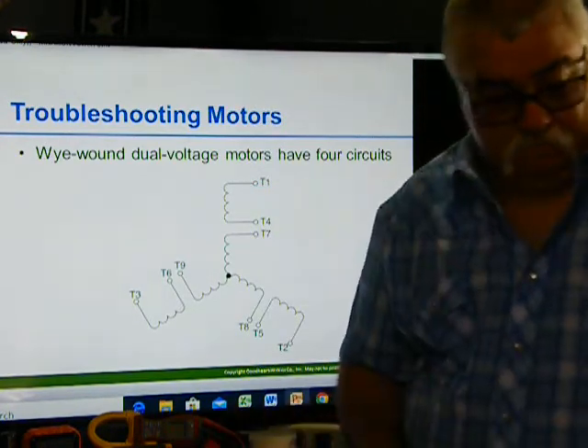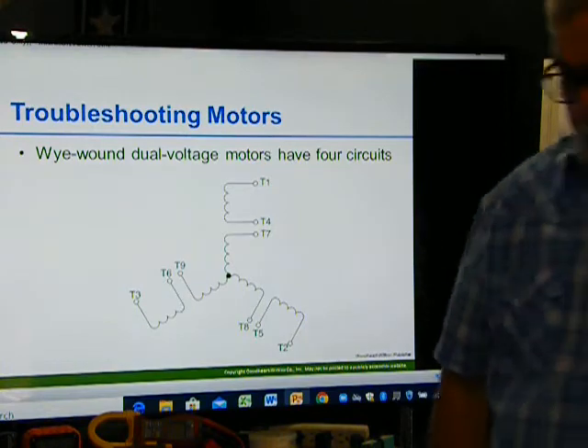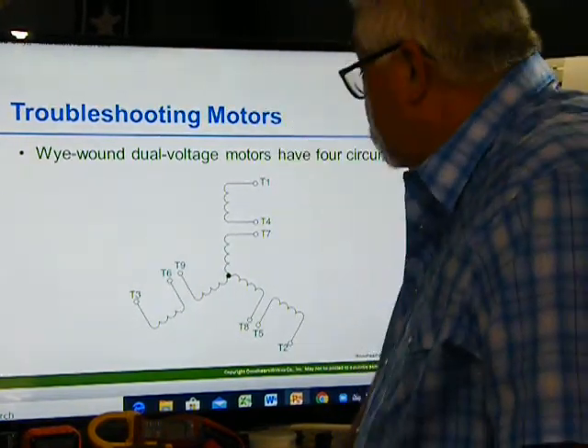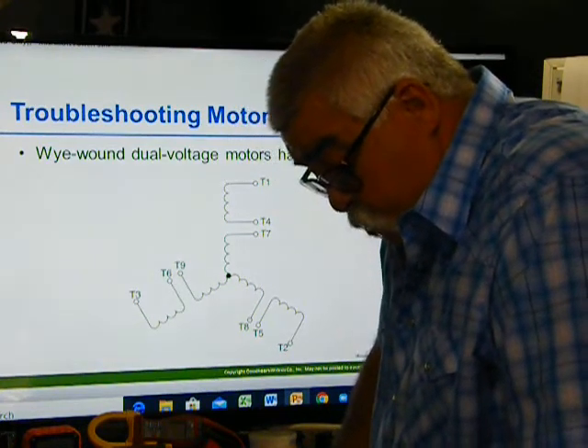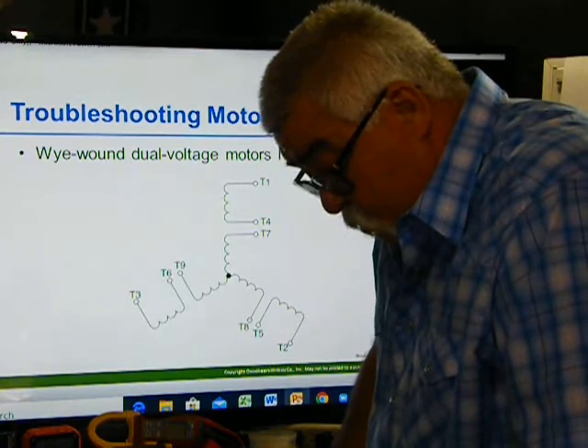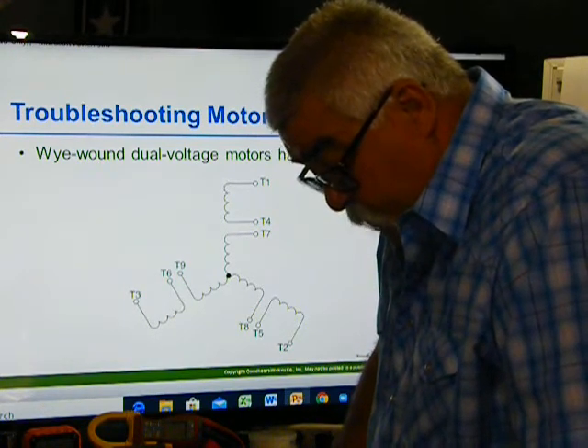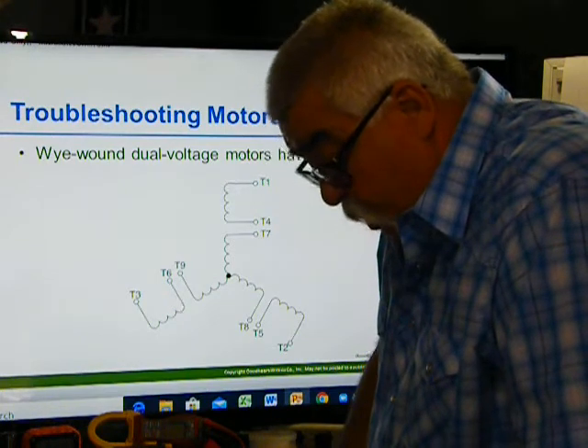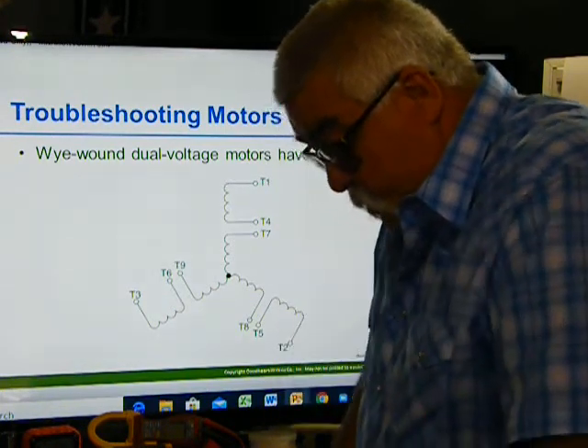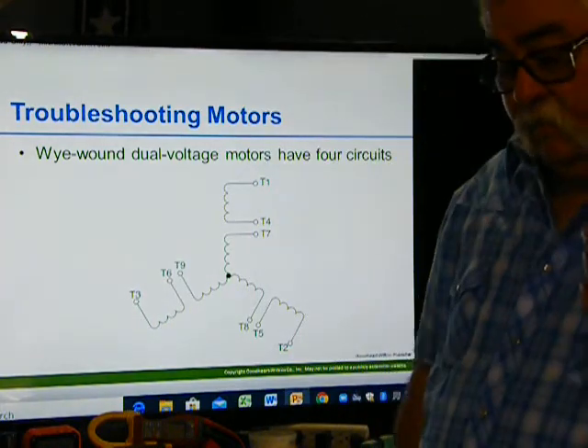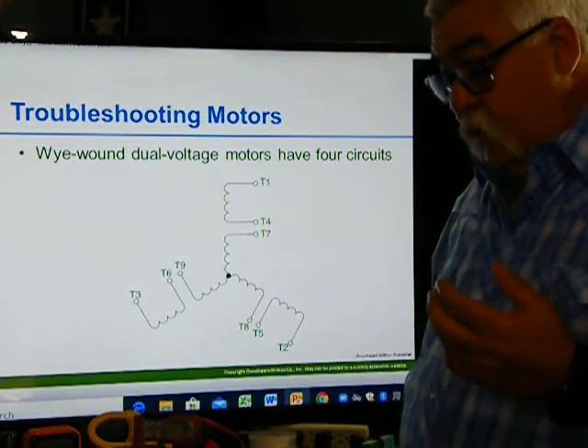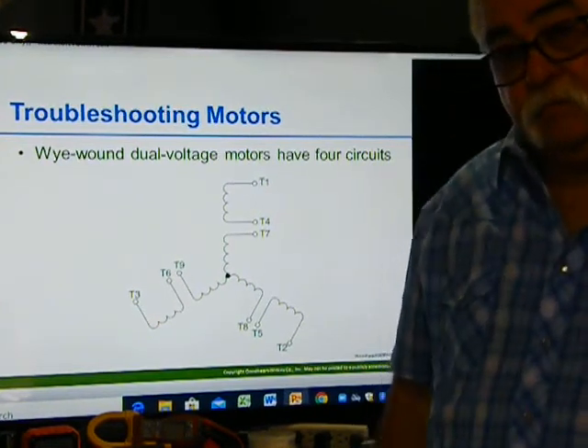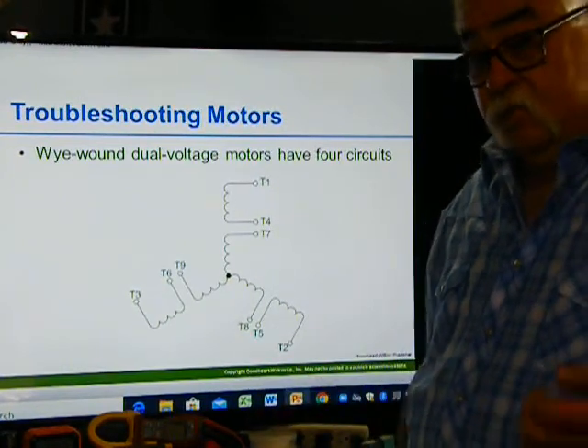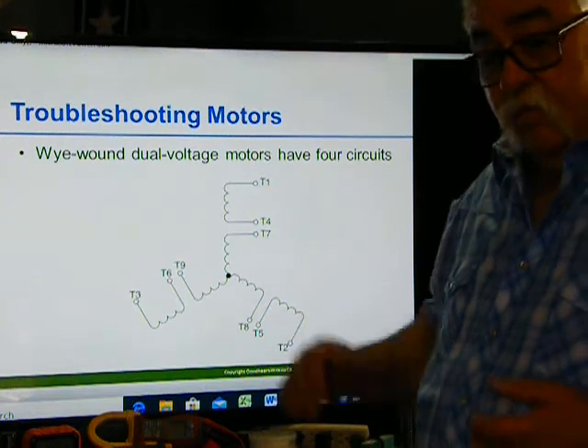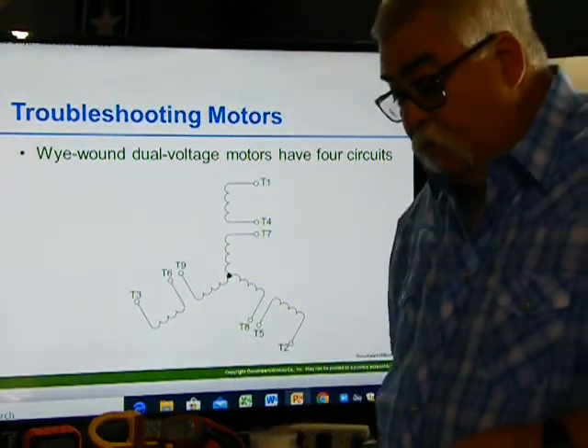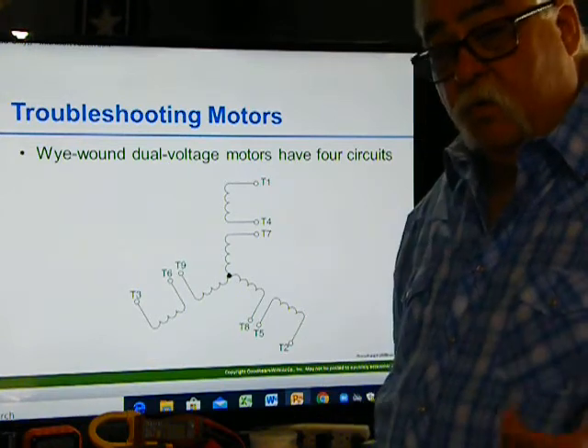Alright, troubleshooting motors. It is fairly difficult to distinguish dual voltage motors as Y wound or delta wound when identifying tags are no longer visible or missing. However, there is an easy way to check. When you have a delta motor, the windings are different from a Y motor. One is a 120/208 or a 277/480 or a 240/480. Your windings are different depending on your input voltage. So how is your motor? Is your motor a Y or a delta?